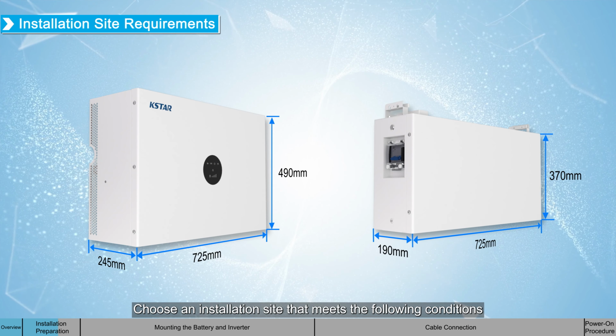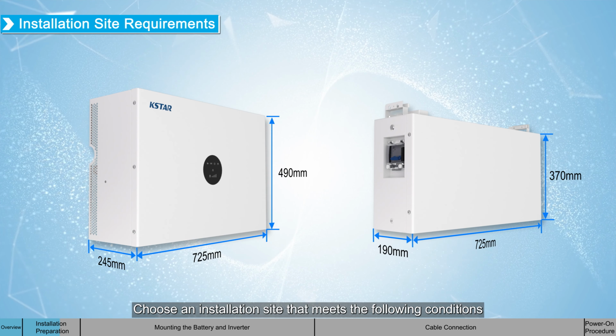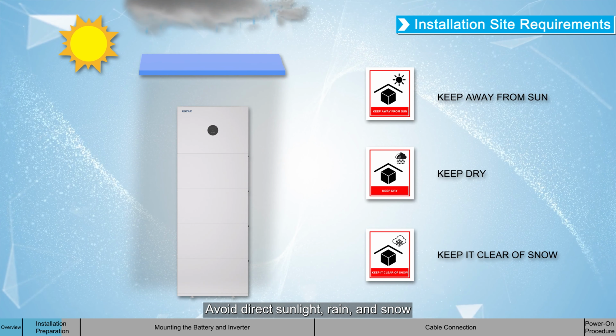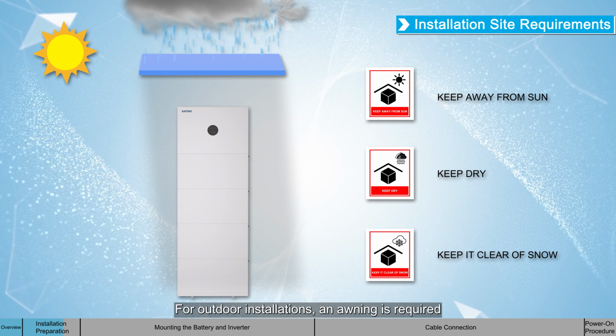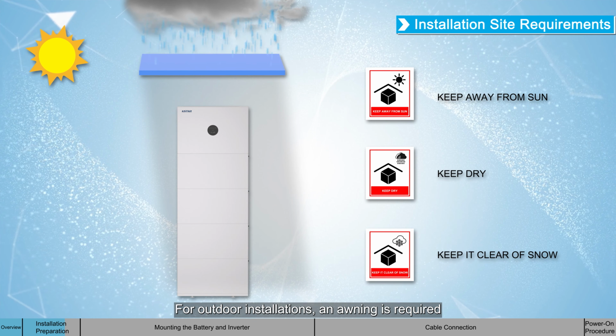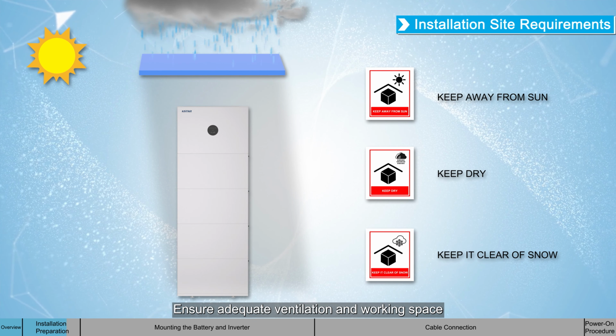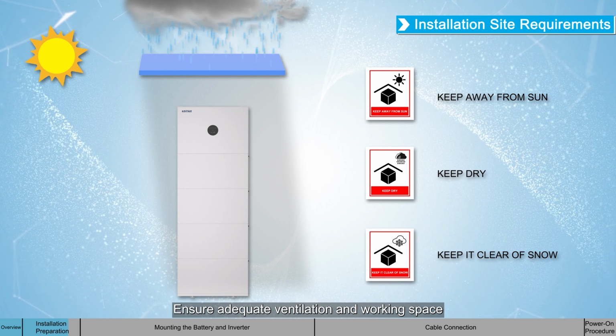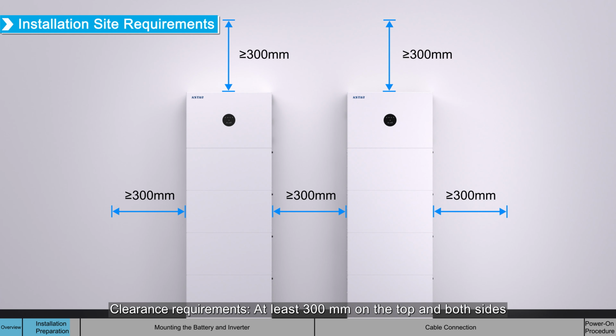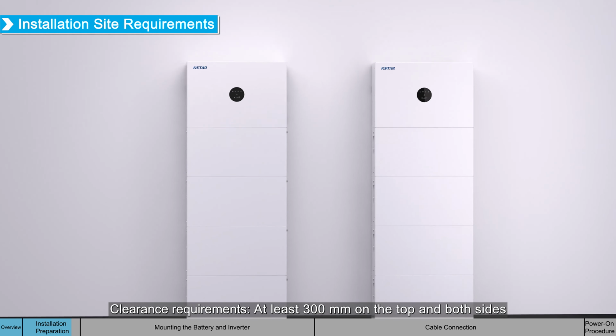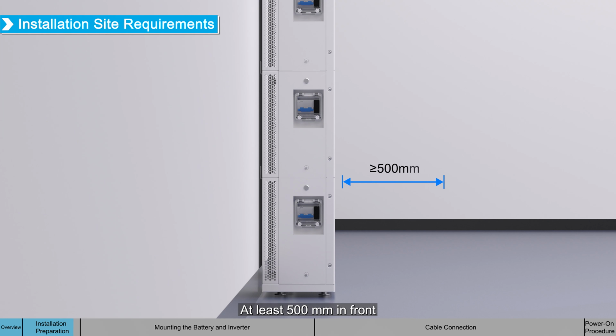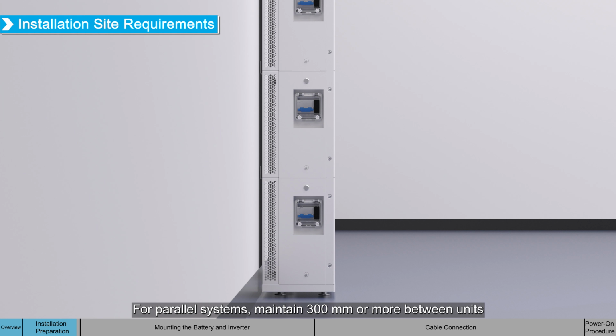Choose an installation site that meets the following conditions. Avoid direct sunlight, rain, and snow. For outdoor installations, an awning is required. Ensure adequate ventilation and working space. Clearance requirements: at least 300 mm on the top and both sides. At least 500 mm in front. For parallel systems, maintain 300 mm or more between units.